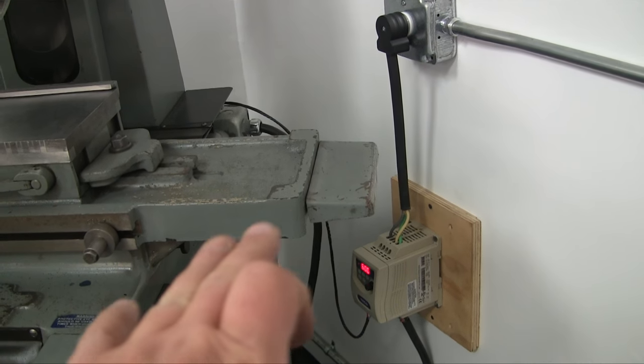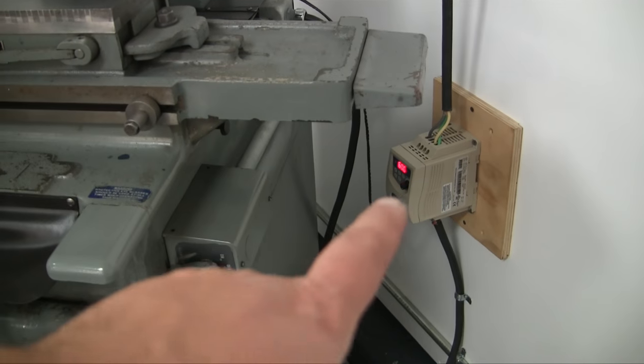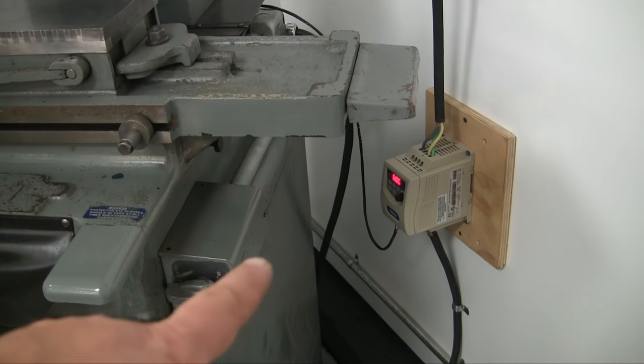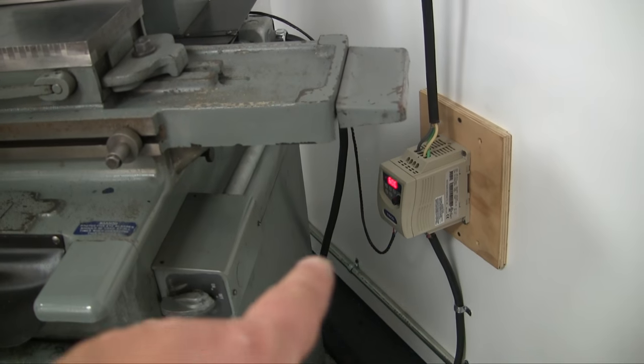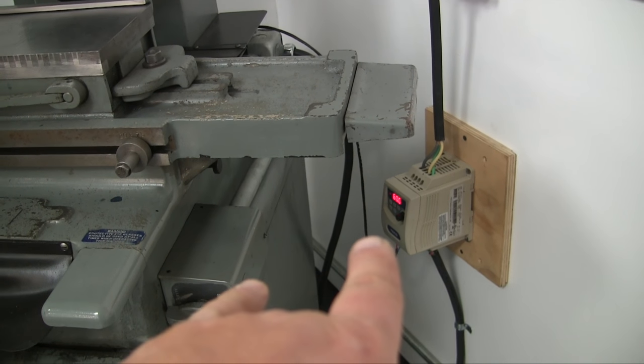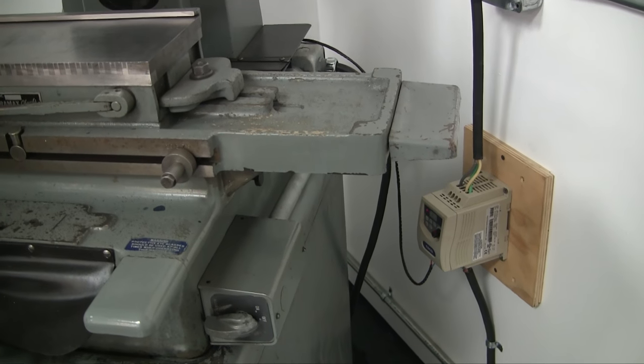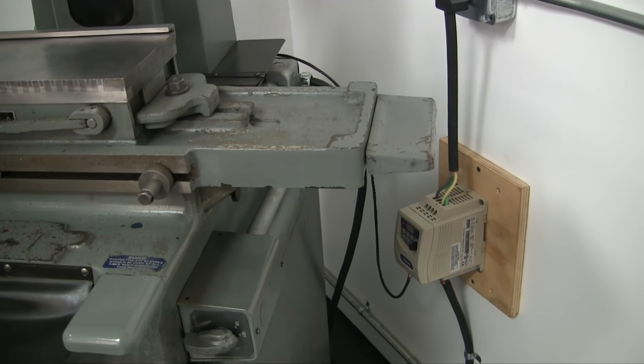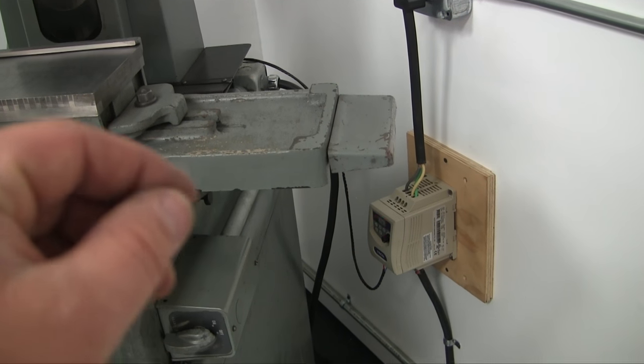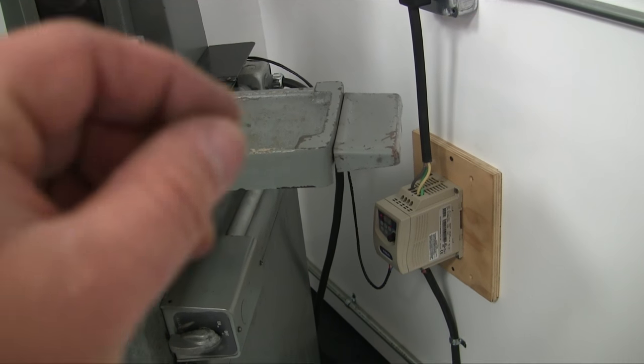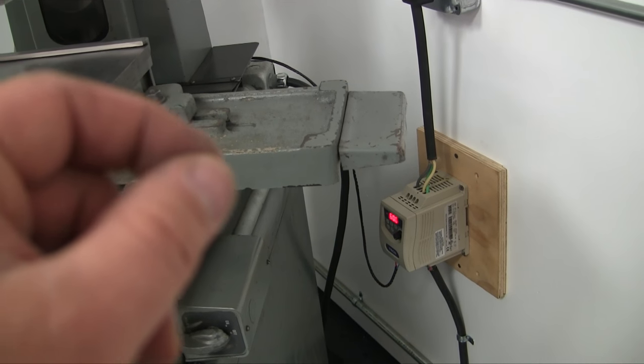Now I don't know 100% sure because it might be hard to tell—there's not a very good line of sight between the VFD and the case of the surface grinder. You're talking about eight inches or so, and if you squeeze your head in there it would be completely blurry, which it is for me. What I did was, because I had this previously hooked up, I went in with my screwdriver and found the terminals that were loosened up, because all the other ones were locked down tight.